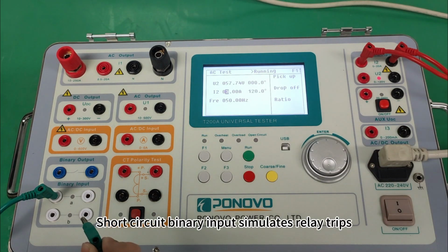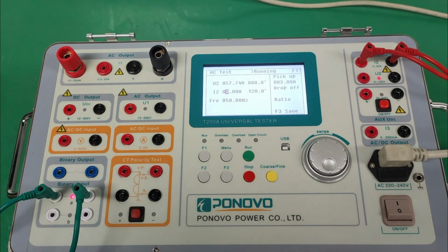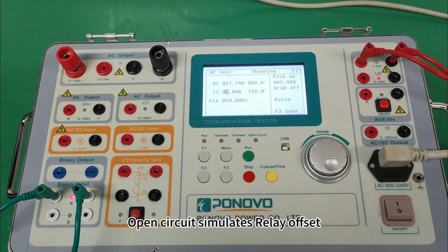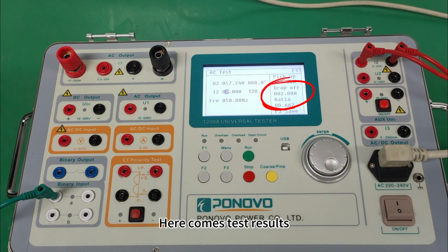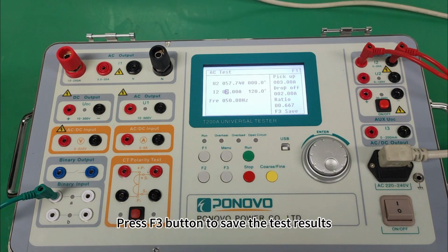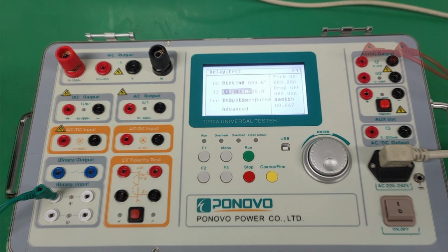Short circuit binary input simulates relay trips. We adjust to 2 ampere. Open circuit simulates relay offset. Here come test results. Press F3 button to save the test results.